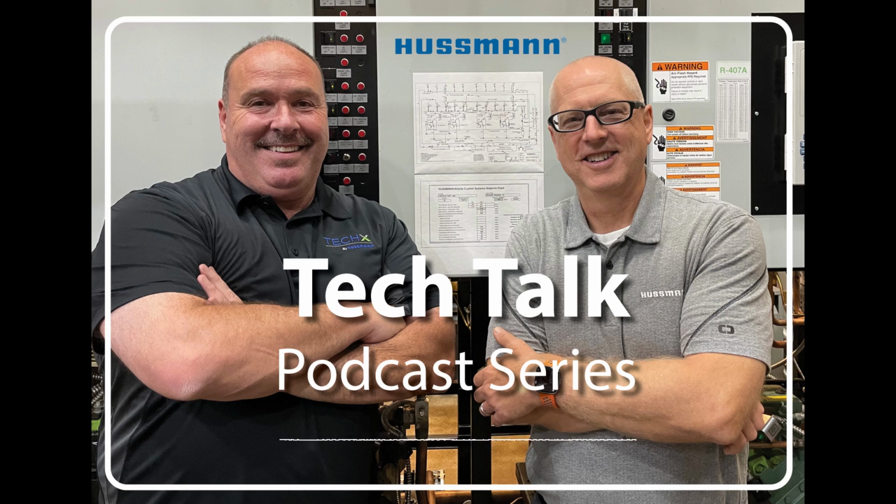Paul, again, it starts with a good preventative maintenance program. Fan motors on most self-contained condensers are fractional horsepower. They're shaded pole, permanent split capacitor, or ECM type motors. These motors are typically hermetically sealed and replaced when failed. Fan blade cleanliness is important as well. Just a thin layer of dust on the leading edge of a fan blade can decrease airflow and efficiency.